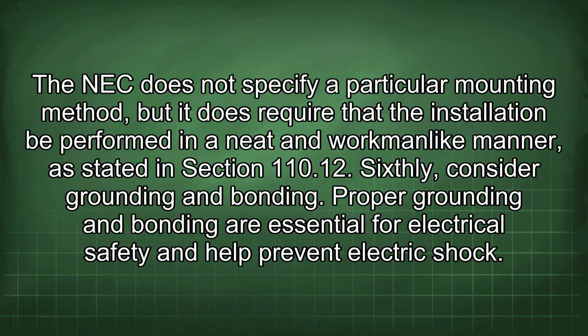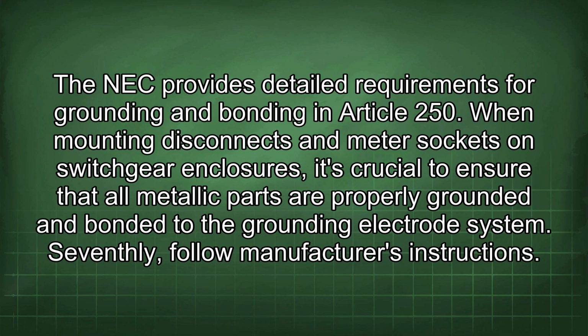Sixthly, consider grounding and bonding. Proper grounding and bonding are essential for electrical safety and help prevent electric shock. The NEC provides detailed requirements for grounding and bonding in Article 250. When mounting disconnects and meter sockets on switchgear enclosures, it's crucial to ensure that all metallic parts are properly grounded and bonded to the grounding electrode system. Seventhly, follow manufacturer's instructions.